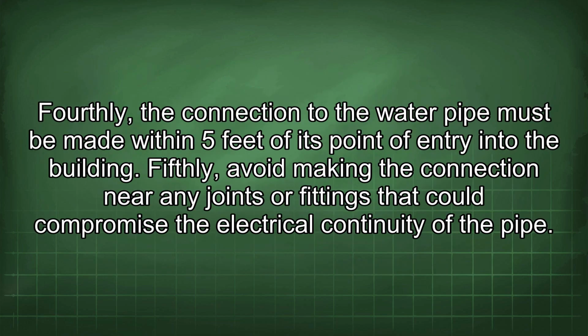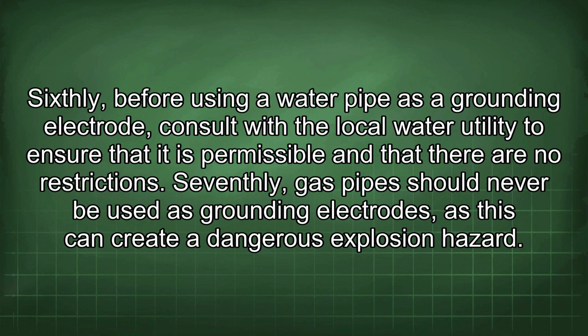Fourthly, the connection to the water pipe must be made within 5 feet of its point of entry into the building. Fifthly, avoid making the connection near any joints or fittings that could compromise the electrical continuity of the pipe. Sixthly, before using a water pipe as a grounding electrode, consult with the local water utility to ensure that it is permissible and that there are no restrictions. Seventhly, gas pipes should never be used as grounding electrodes, as this can create a dangerous explosion hazard.